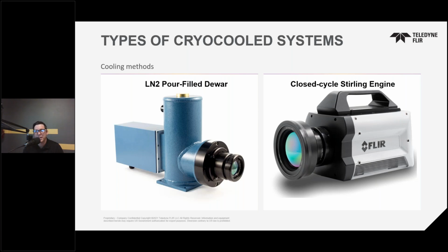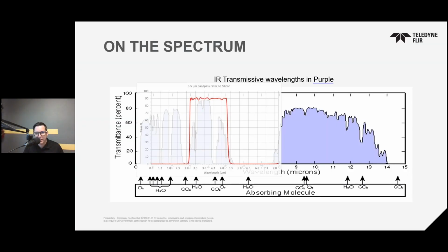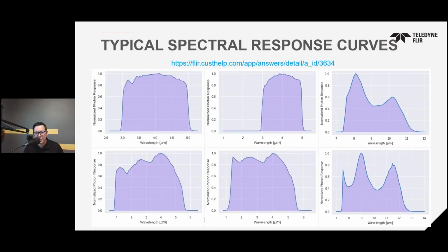That said, again, there's a lot more maintenance to it. You can't just put it in any position. And it's really only useful if you've got a bunch of focal plane array, readout integrated circuit sandwiches, and all of the filters that you need, and you were very well versed in that. From a usability standpoint, closed cycle is much better. Let me get back to where I was now. Okay.